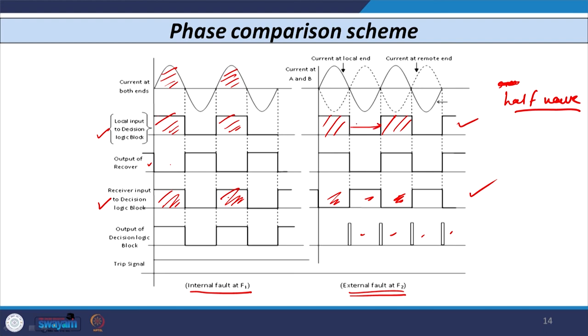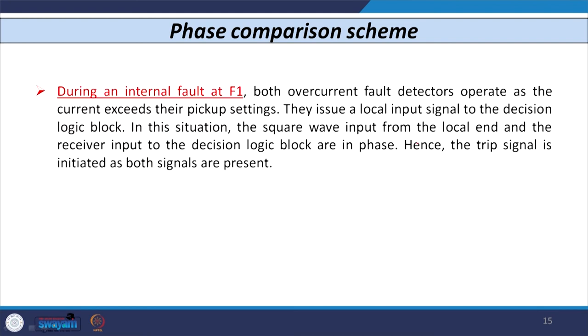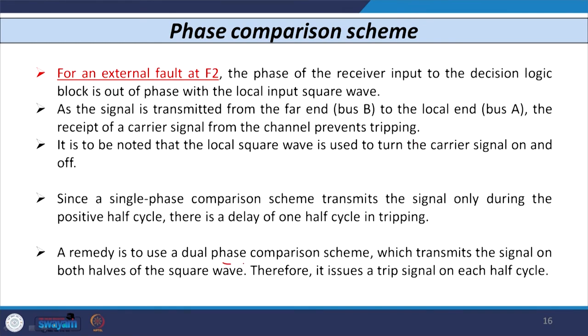That is why this type of scheme is known as a single-phase or half-wave phase comparison scheme, because the signal is transmitted every half cycle — introducing a half-cycle delay. To rectify this, a dual phase comparison scheme can be used, where signals are transmitted for every positive and negative half cycle. We started our discussion with different types of pilot signals (radio frequency, microwave, fiber optic, satellite), then the wire pilot relaying scheme and its limitations, then the carrier current protection scheme including the phase comparison scheme. The directional comparison scheme will be discussed in the next class.